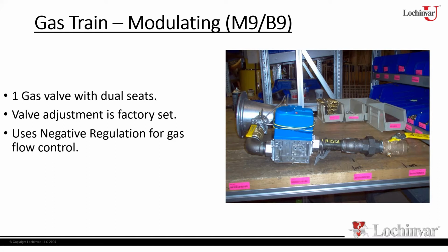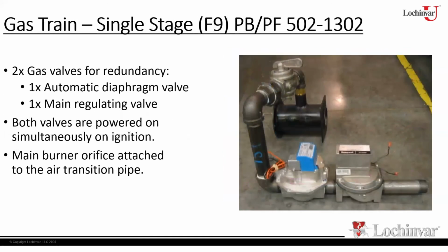All right. Now, the valves that we're using here are dual valve seats. So that's why you just have a single gas valve. The blue one here actually has 2 indicator lights on it to let you know that the valve seats are actually energized. So a single valve, 2 valve seats. Now, when we go to the F9 gas train for the smaller models, and you won't run into these very often, but they are out there, here you've actually got 2 gas valves.